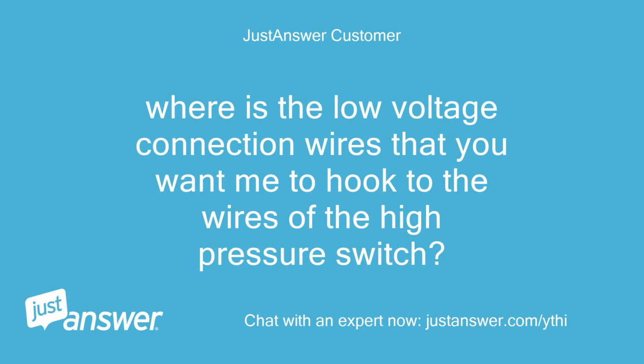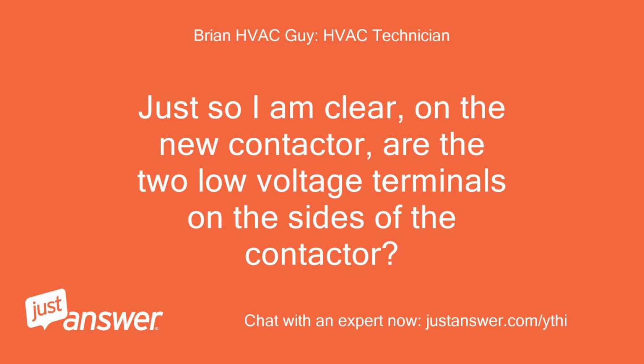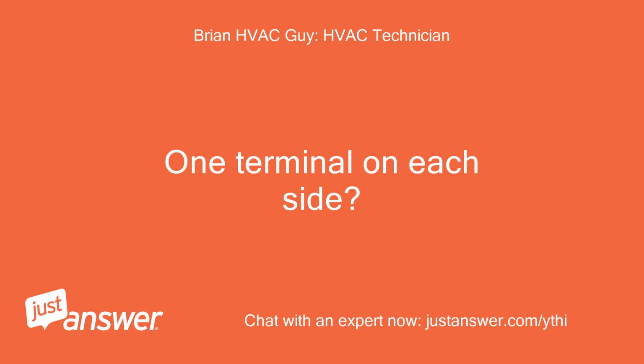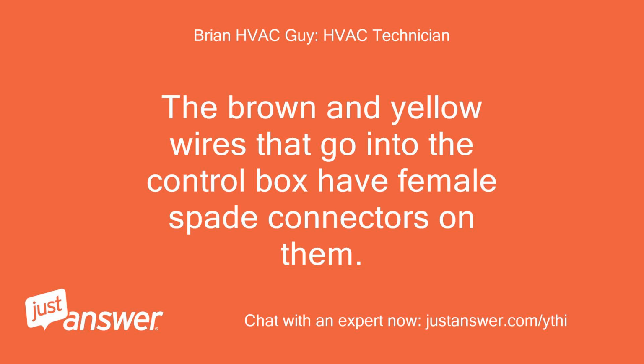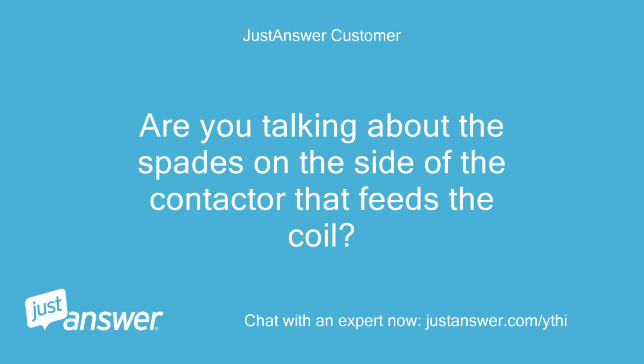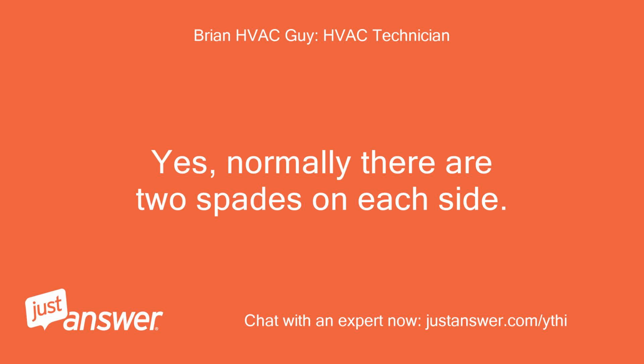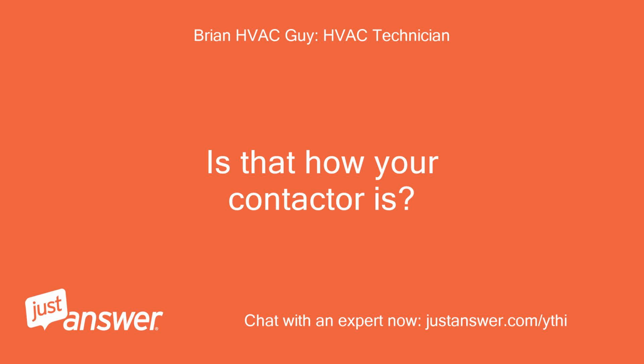Where's the low voltage connection wires that you want me to hook to the wires of the high pressure switch? Just so I am clear, on the new contactor, are the 2 low voltage terminals on the sides of the contactor? 1 terminal on each side? The brown and yellow wires that go into the control box have female spade connectors on them. Are you talking about the spades on the side of the contactor that feeds the coil? Yes, normally there are 2 spades on each side. Is that how your contactor is? That is correct.